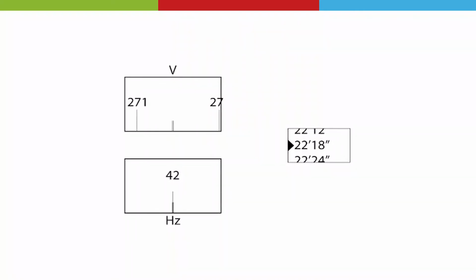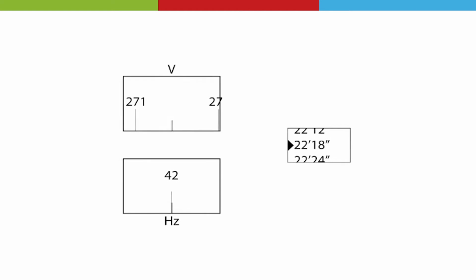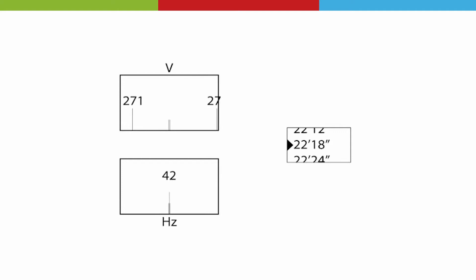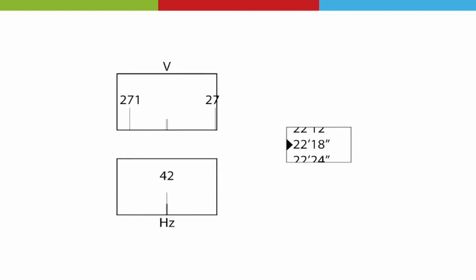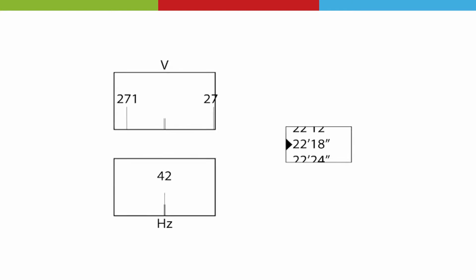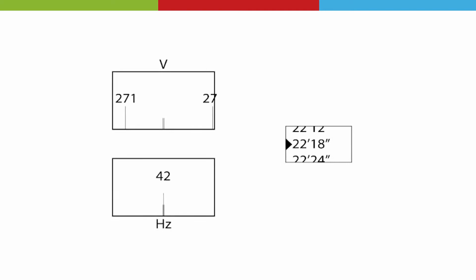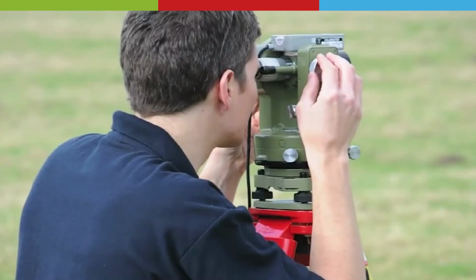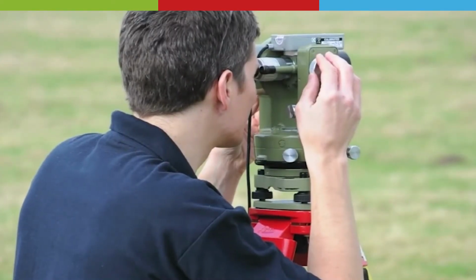Use the micrometric control to bring the horizontal degree reading within the double line index. Then read the degrees in the horizontal window followed by the minutes and seconds. Here the reading is 42 degrees, 22 minutes and 18 seconds. Because the circle is on the left, this is called the circle left reading.